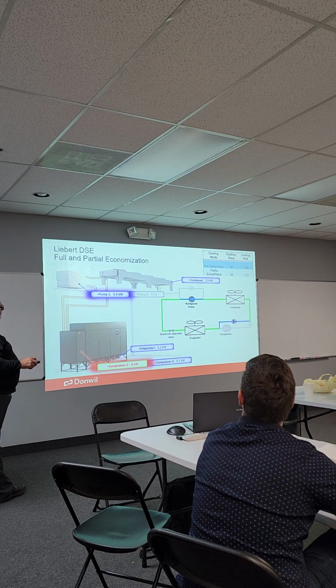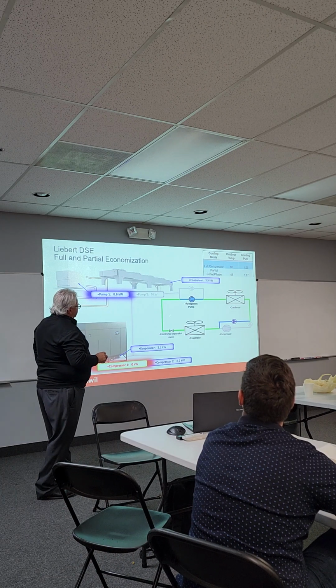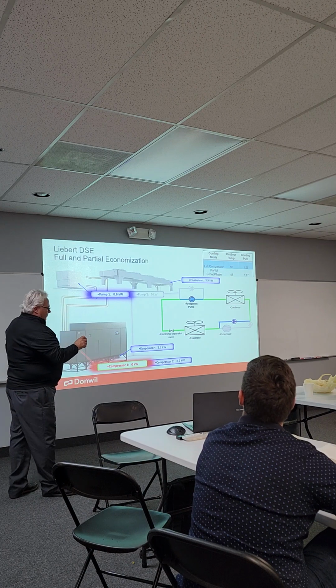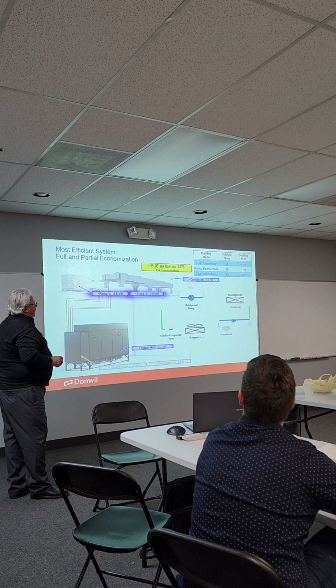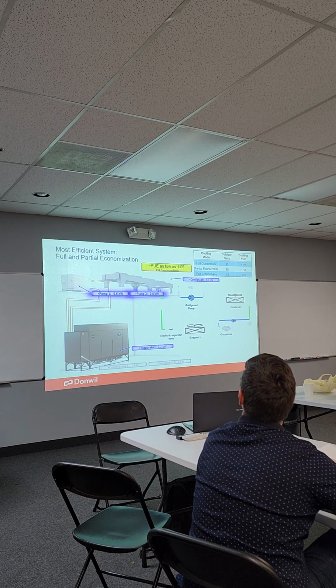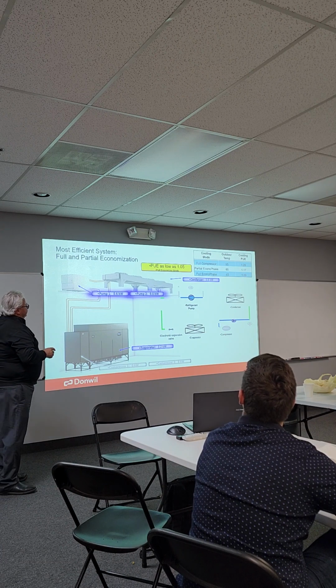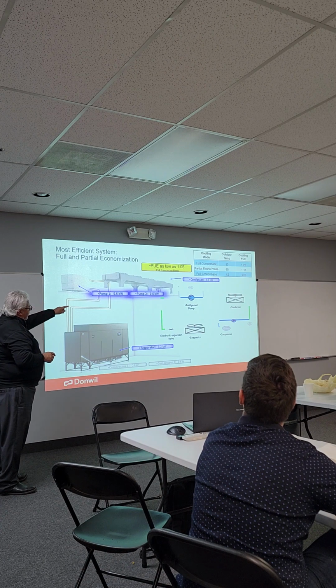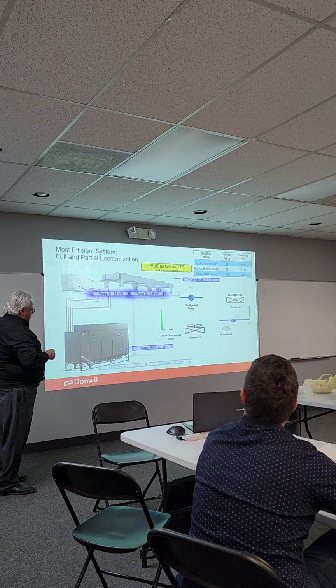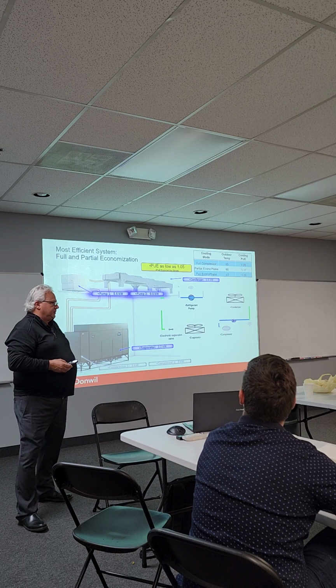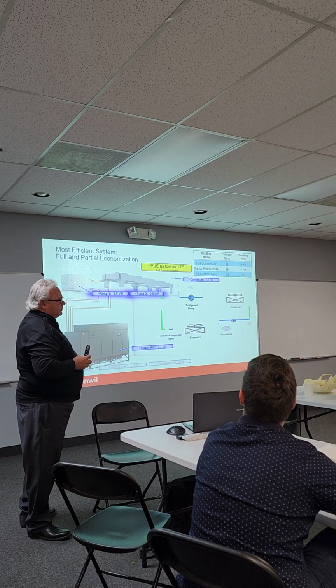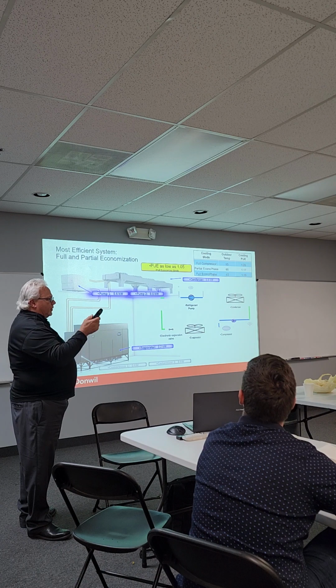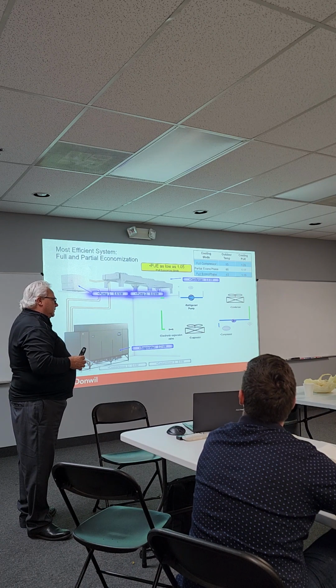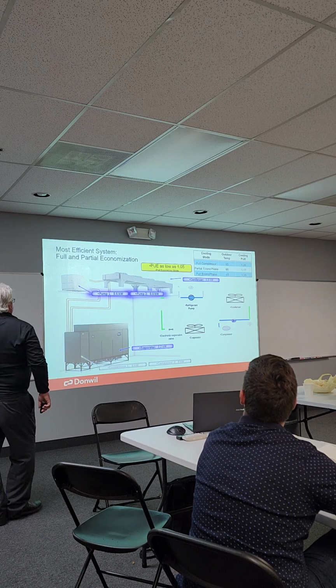And here's your basic refrigeration cycle. If we go to a 45-degree day, again, this is depending on what's going on in the room. On a 45-degree day, we can run both pumps and we shut both compressors off. And everybody says, how can you do that? When you think about it, we're just pumping refrigerant like the compressor does. Still have a change of state, but we are cooling that down with the temperature outside. 45. Yep. To get where we need to be.